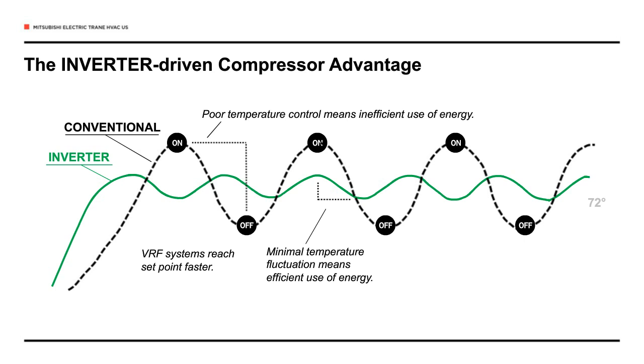By ramping up power to the compressor when needed, an inverter provides a more accurate, on-demand approach to temperature control. If your room temperature is already a comfortable 72 degrees, for example, an inverter may slow the compressor's engine to a crawl. If your room is really warm, say 85 degrees, the inverter will push the compressor into high gear, reducing that temperature more quickly. This is another source of energy savings, as this eliminates the energy-intensive start and stop cycles of conventional HVAC systems.